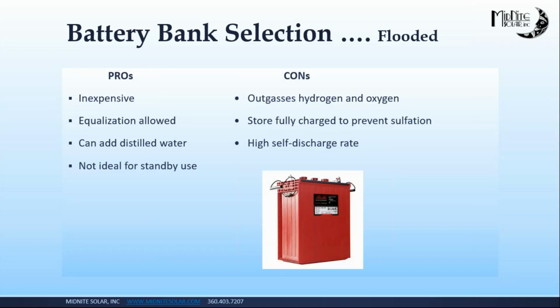Because the batteries are flooded and have these caps, you can actually measure the specific gravity with a hydrometer, which is really the best way to ascertain the health of your batteries. With a sealed battery, all you can do is measure voltage. But with a flooded battery, you can measure both voltage and specific gravity.